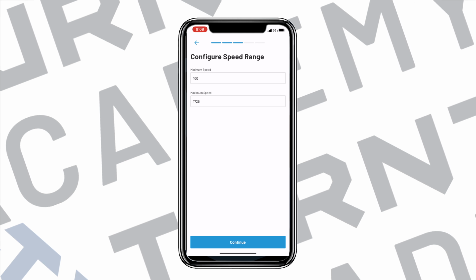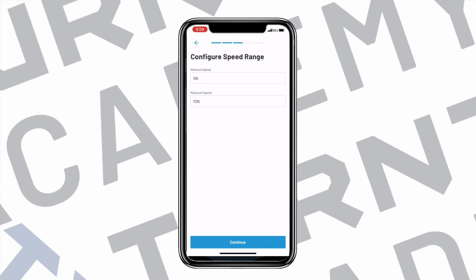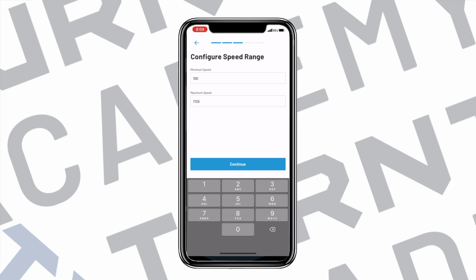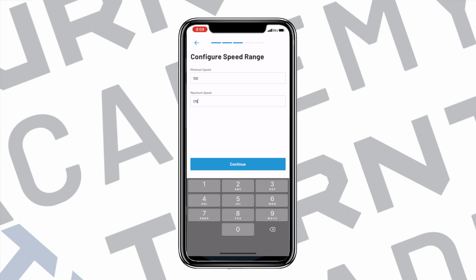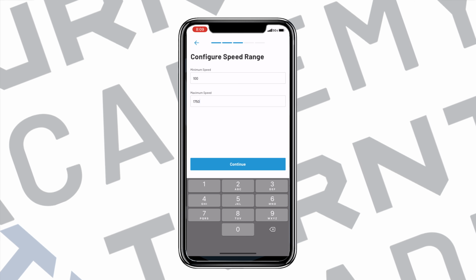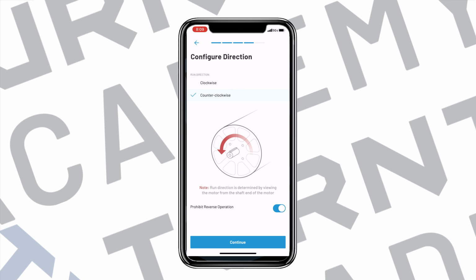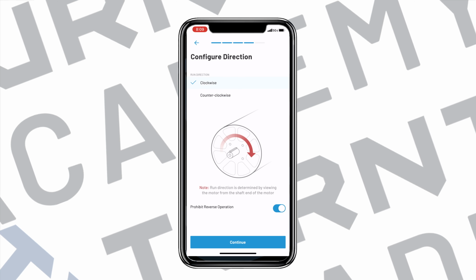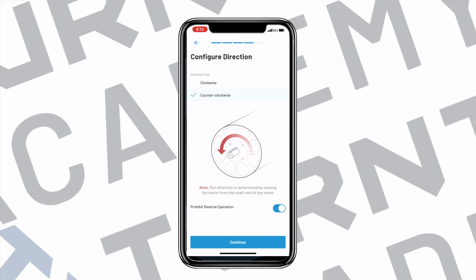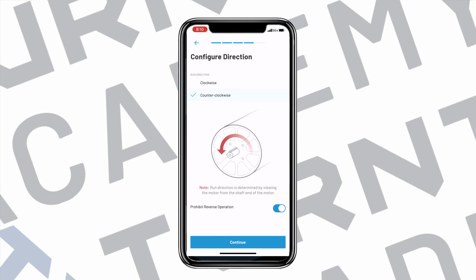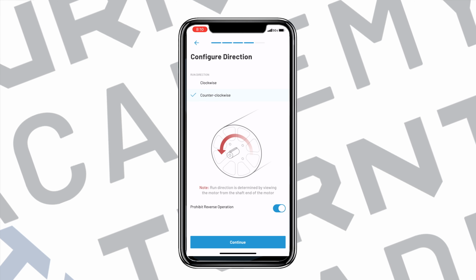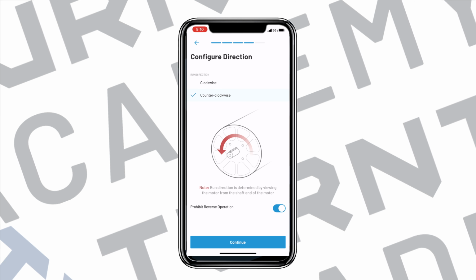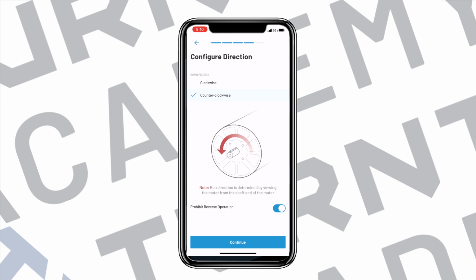Now, configure the motor speed range. Do not change the minimum speed. Enter the original induction motor speed as the maximum speed and touch Continue. Set the run direction as viewed from the motor shaft end. The prohibit reverse operation remains enabled. There are very few applications where the motor needs reverse operation.